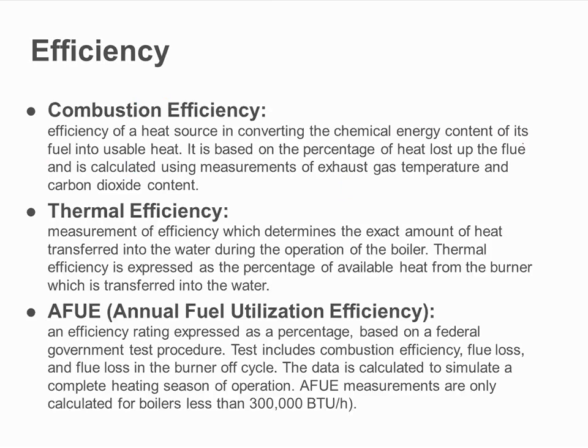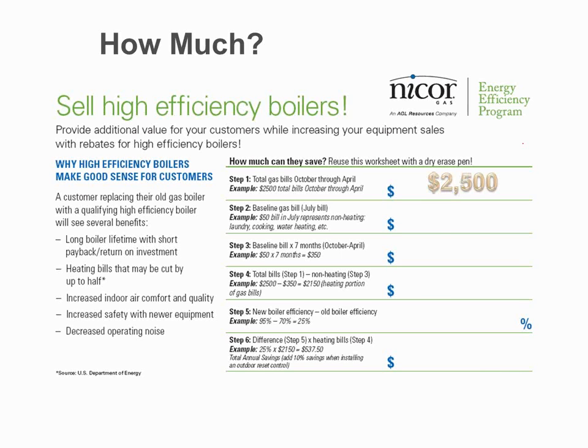But basically, you've got to get someone's utility bills for the winter months, right? So October through April for most buildings that are light commercial and residential. So if I go to someone's house and I get all their bills from October through April, and they're buying $2,500 of gas, that's nice, and I know that, it's wonderful, assuming they can give me their bills. But I also need one of their summertime bills, right? I need that because I have to back out all the gas usage that has nothing to do with the boiler. Water heating, stoves, dryers, whatever. All right, so I take those $50 times the 7 months, $350 out of the $2,500 has nothing to do with space heating. That means $2,150 is space heating.